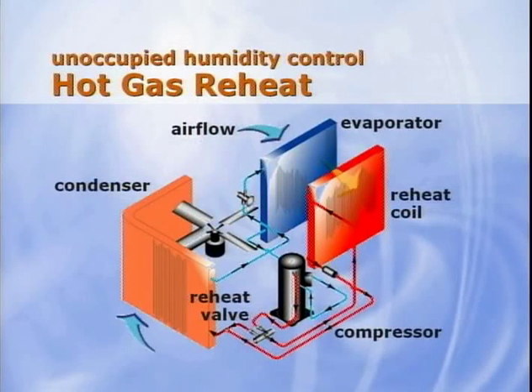When after-hours dehumidification is needed, the rooftop unit turns on and diverts hot refrigerant vapor, leaving the compressor, through a refrigerant-to-air heat exchanger that is located in the airstream, following the evaporator coil. Sensible heat is transferred from the hot refrigerant to reheat the dehumidified air leaving the evaporator. This strategy uses heat recovered from the refrigeration circuit to reheat centrally. It saves energy by avoiding the use of new energy to reheat remotely at the VAV boxes. It also allows the boiler and pumps to remain off.